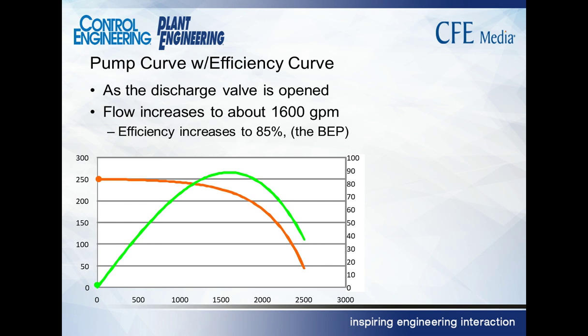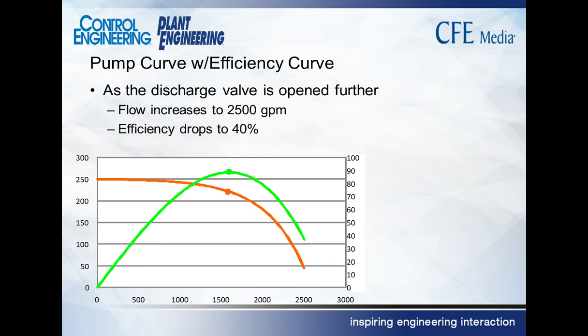On this pump, that occurs at about 85%. Now, beyond this, I can continue to open up the discharge valve and get more flow. I'll get more flow through the pump, but it's going to take more and more energy to get it because the efficiency is going to be dropping. Efficiency will never make it back to 0 because there is some work being done by the pump. So efficiency is a function of the amount of flow through the pump, and there is a best efficiency point.